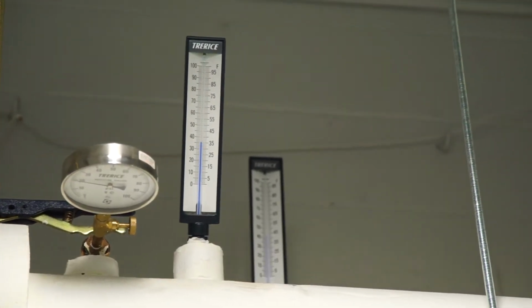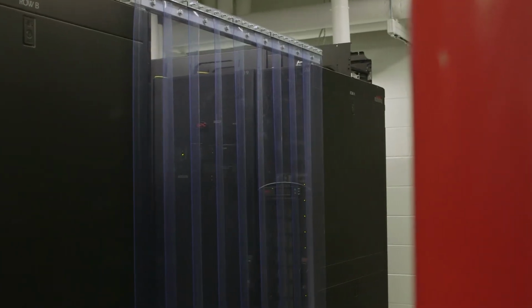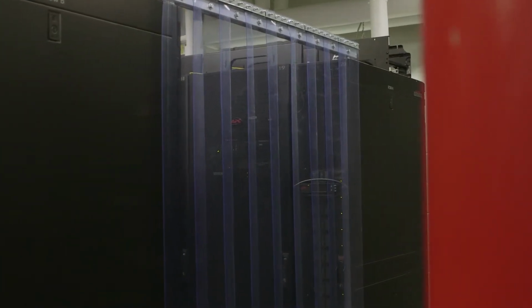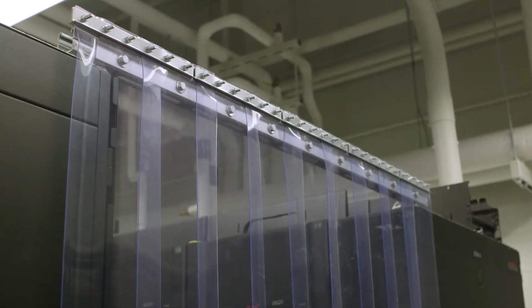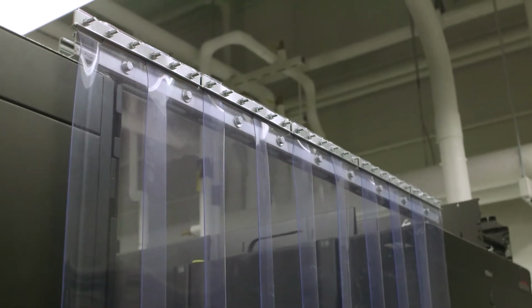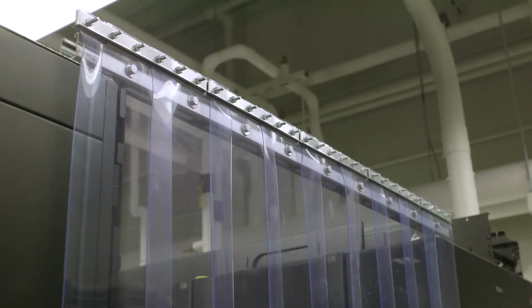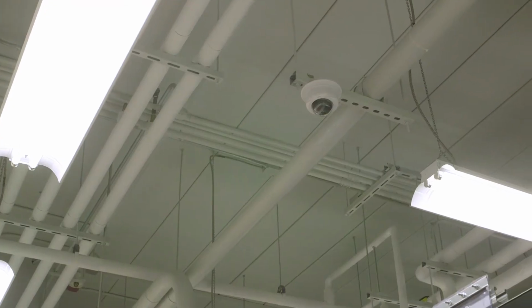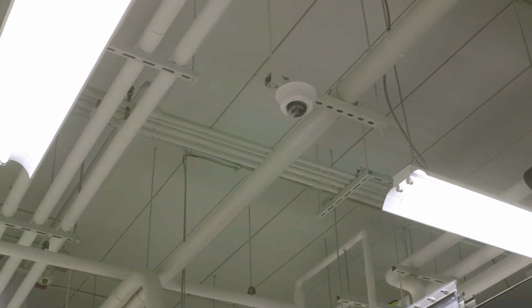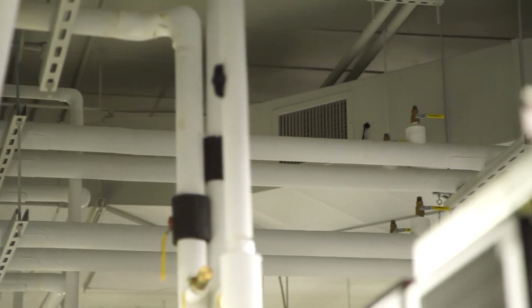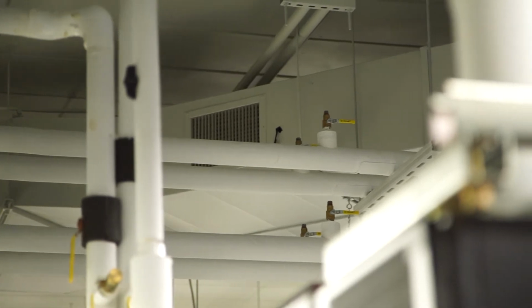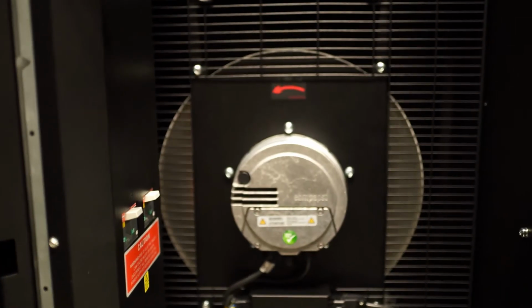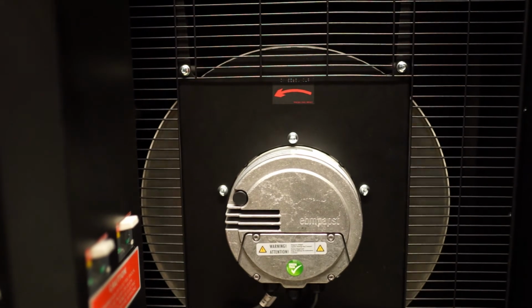In addition to the interior and exterior chillers, DC-1 also has cold aisle containment curtains set up to prevent the mixture of hot and cold air at the ends of each respective aisle. This helps in maintaining a stable temperature. We also left the high ceilings in this room exposed to allow for additional heat dissipation above the racks. As a final backup, we have forced air cooling that can be engaged if anything happens to the inline chilling system. With Data Center 1, you can rest assured that your data is stored in a facility running at optimum temperatures. Your data is vital to your business.